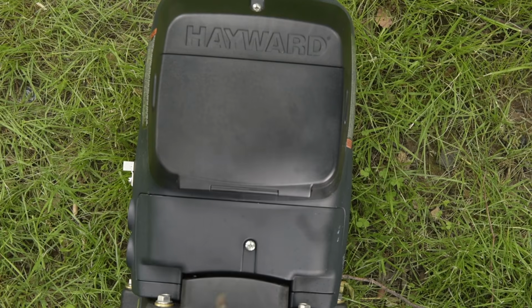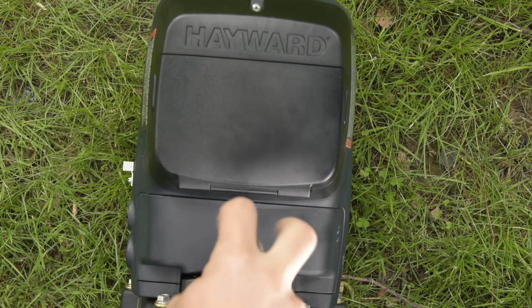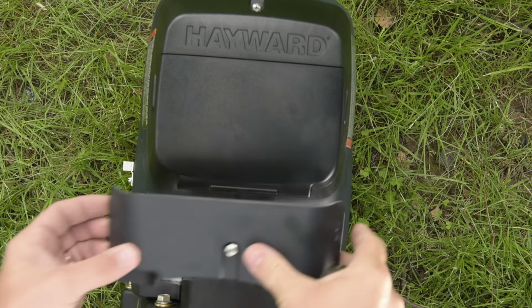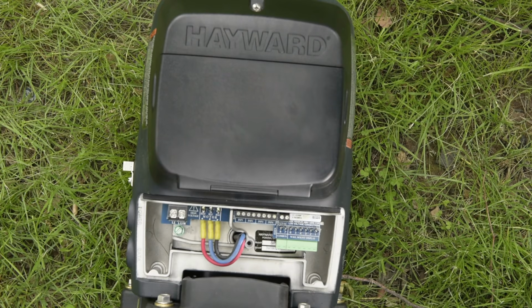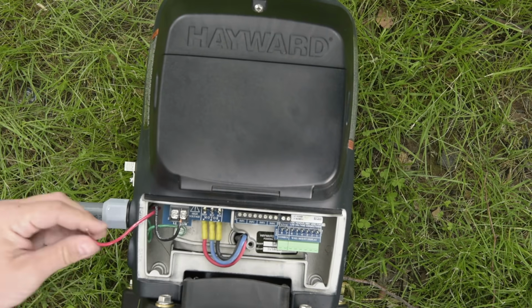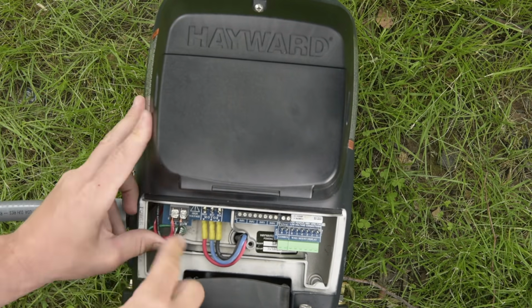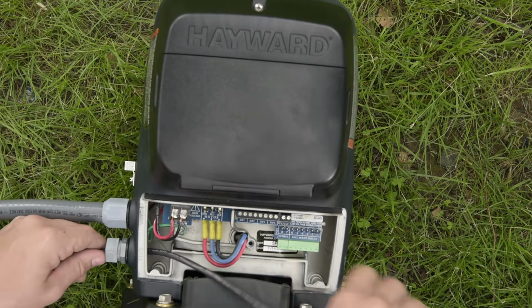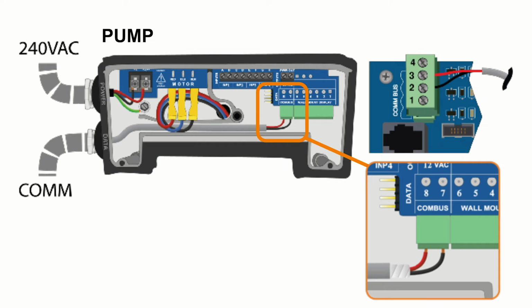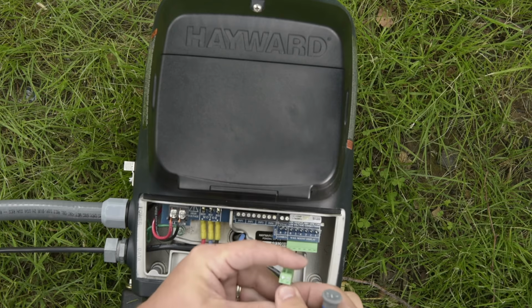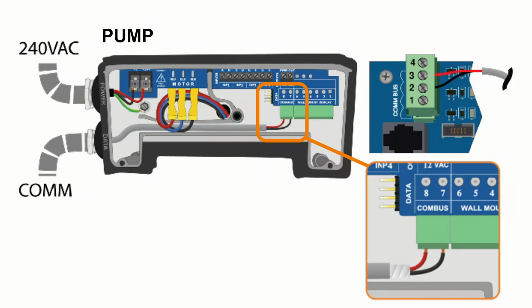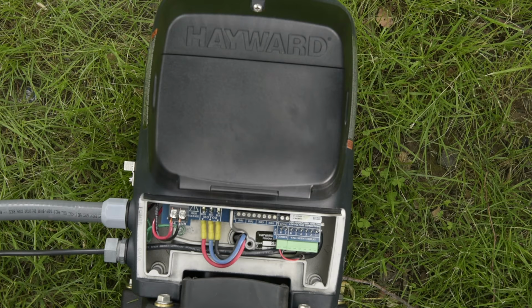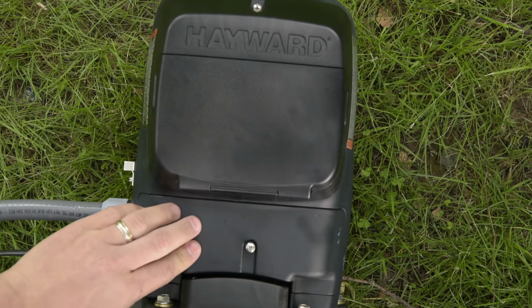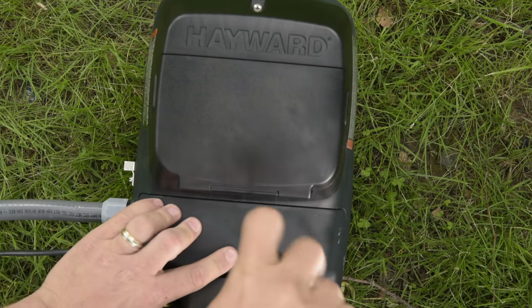The following instructions are for the TriStar VS950 Omni only. Unthread the single screw to remove the cover plate and reveal the variable speed pump's wiring compartment. Wire the high voltage wires to L1 and L2 as shown. Also connect the ground wire. Now we need to connect the COM wires ran through the COM conduit between the VS pump COM bus and the wiring hub. The wires are connected as follows. COM bus 7 pump to 2 on the VS Omni wiring hub. COM bus 8 pump to 3 on the VS Omni wiring hub. After securing the pump's cover plate, the next few steps will outline the low voltage connections.